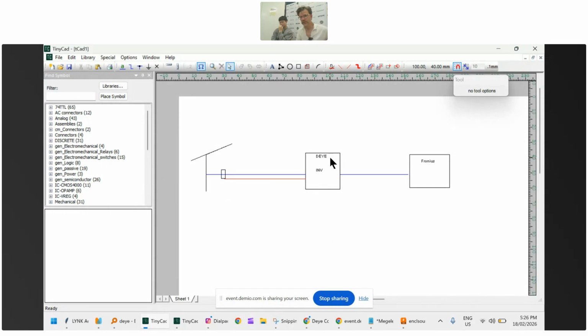That's pretty straightforward. When the grid goes down, the Deye is then in control of the AC waveform, and it can use frequency shifting to ramp the Fronius up and down, prevent the batteries from being overcharged, and control it. And you don't need any comms between the two of them in order to do that.